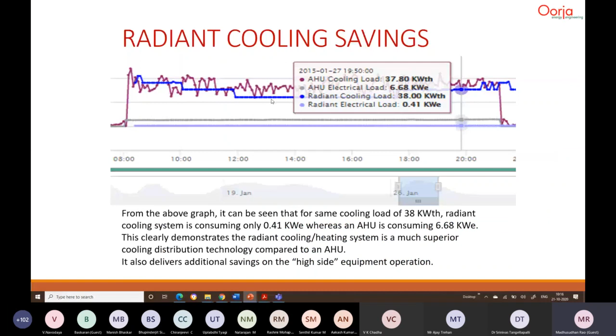And as I said, there is also a saving on the chiller side. Earlier, it had to provide 7 degrees centigrade water because you wanted a low temperature in the coil. Now, as you can see in this graph, the temperature of 24 degrees in the space is being maintained throughout the day, more or less between 27 and 24, even when your floor supply temperature, which is roughly equal to floor temperature, is around 22 degrees centigrade. So what that means is the chilled water, which was earlier supplied at 7 degrees centigrade, can now be supplied at a much higher temperature, which can be 15 degrees, 16 degrees, or even 20 degrees.